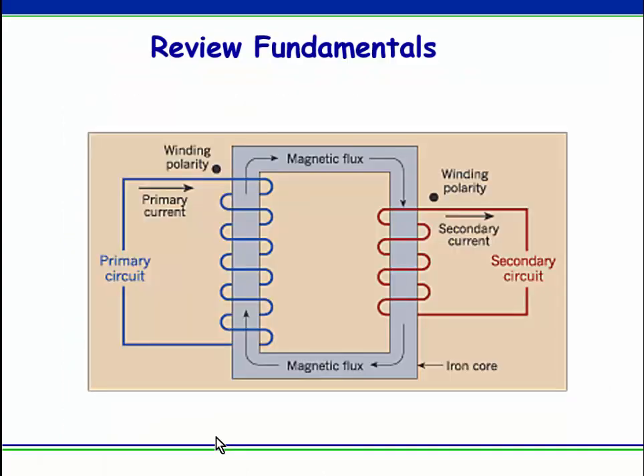Okay, just looking really quickly, remember power transformers are isolation transformers. There's no electrical connection between the secondary and the primary circuit. I'm not going to do a transformer theory class for you. You've already done that. But a couple things you need to know when you're banking transformers and working with transformers: you have to remember that they are totally separate circuits. That's why we often ground the secondary, because it's a separately derived circuit. There's just a magnetic connection.